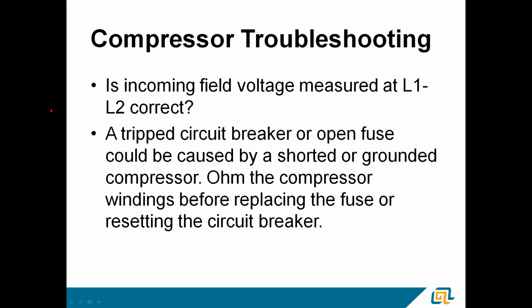When I was a young technician, I went to a job early in the morning, thought this is great, I could slam in a fuse, I'll be out of here in 20 minutes, no problem. Well, it turned out that that compressor was shorted. And when I powered the compressor up, I actually blew the little fusite, the terminal block, right out of the compressor. And at 7:30 in the morning, I was showered with refrigerant oil and refrigerant. And I learned that lesson.